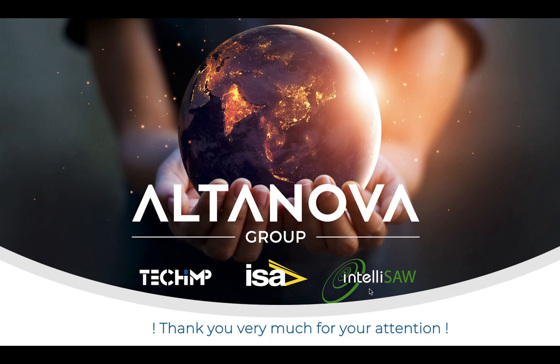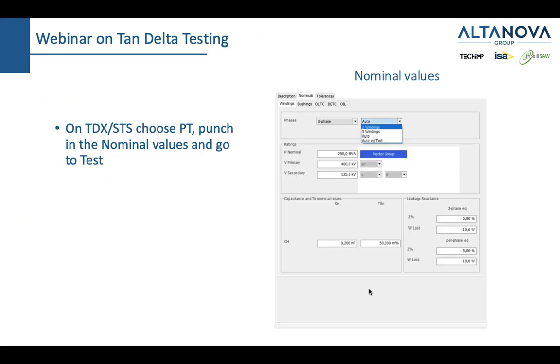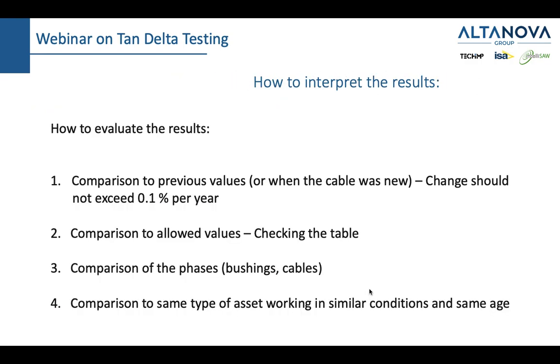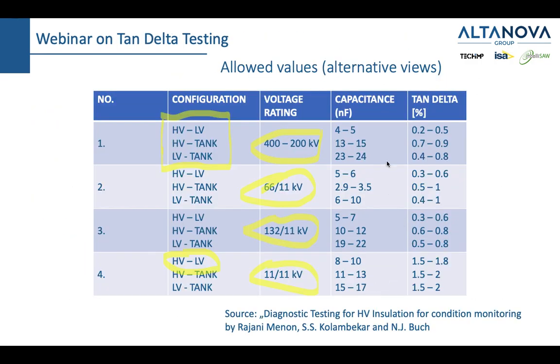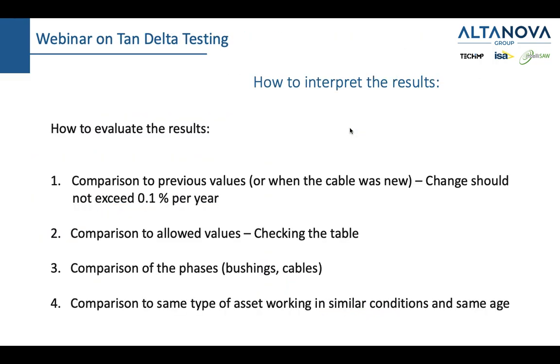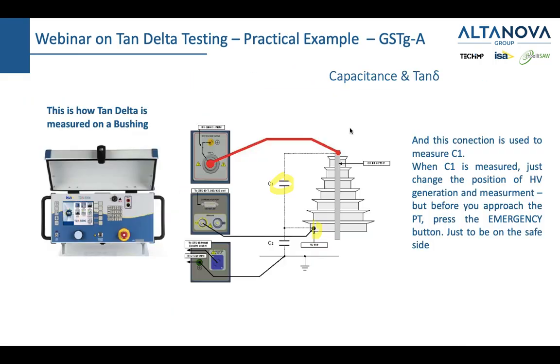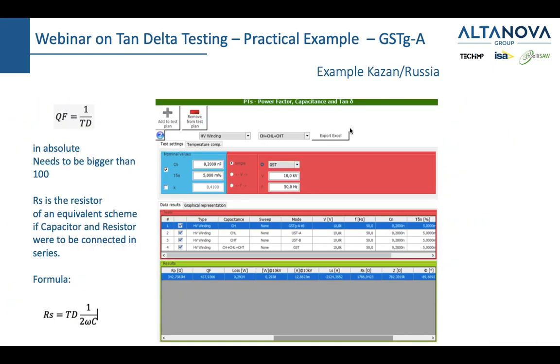What is the maximum capacitance to which 12 kV can be connected from the kit? So the maximum capacitance is a little bit less than 100 nanofarad. So between 90-95 to 100 nanofarad is the maximum capacitance. We saw before that these capacitances are much less than that, even if you sum them up. So let me check. Here we see that the biggest capacitance is, let's say, 24. So if you sum up this, this, and this, you would still be far away from 90, even if you have a transformer with primary, secondary, and tertiary windings.